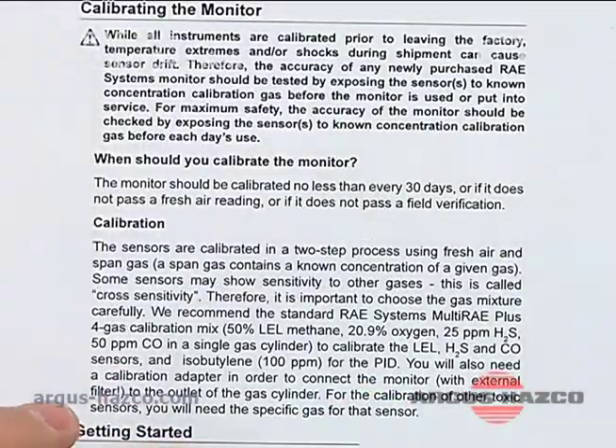It's very important on your MultiRAE that you configure it to those gas readings, so that when you do a multiple sensor calibration it's setting it to the known concentration in the cylinder.